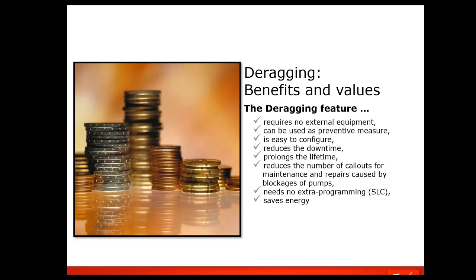Benefits of using the deragging in the FC202: the deragging feature doesn't require any external equipment to enable it or use it. Again, it can be used as a preventive. It doesn't have to be clogged. You can set it to run at every start and stop, or just at the starting or just at the stopping. It's very easy to configure. And as seen in one of the handouts, there's a quick, easy way of setting it based on the power tuning feature.